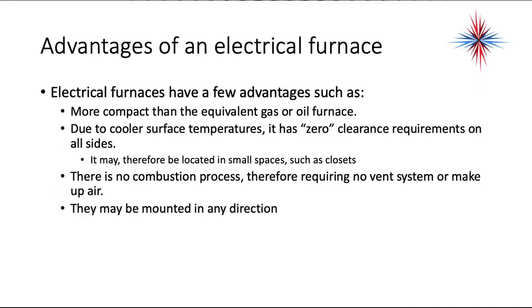Some advantages are that they are more compact than equivalent gas or oil furnaces. Due to cooler surface temperatures, they have zero clearance requirements on the sides. It may therefore be located in small spaces such as closets or even in wall cavities in apartment units. There's no combustion process, therefore they require no vent system or makeup air. They may be mounted in any direction. Horizontal, vertical, downflow, upflow, it doesn't really matter with electric heat.